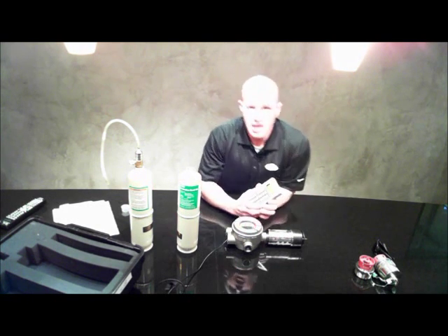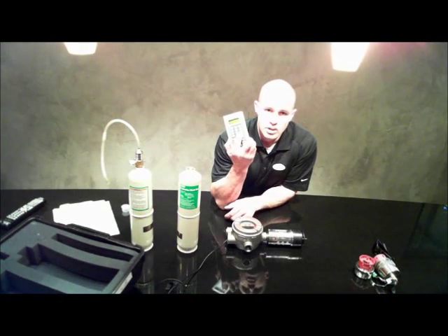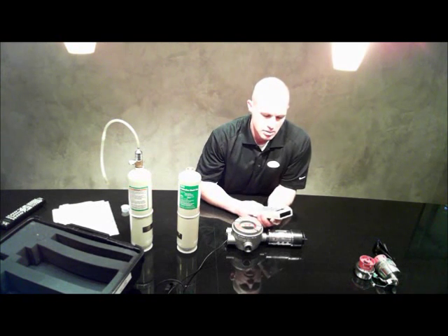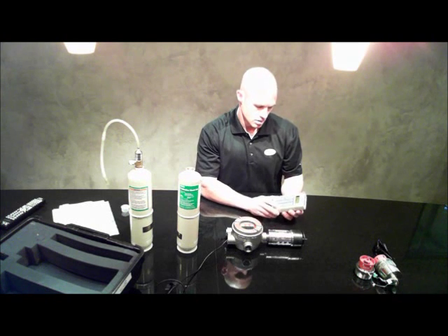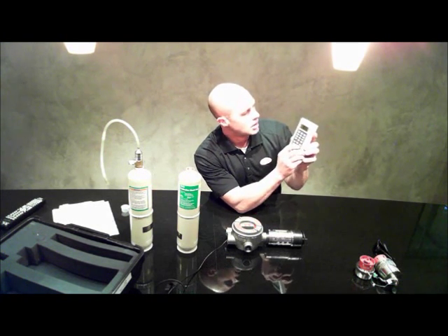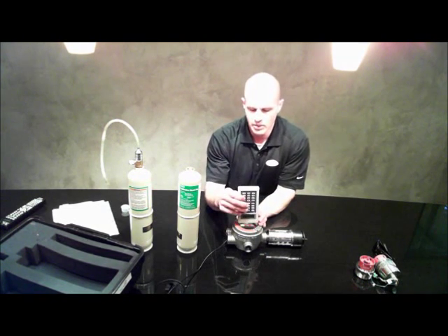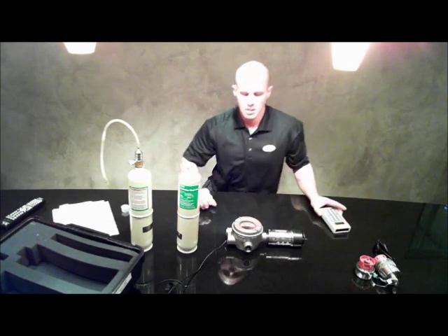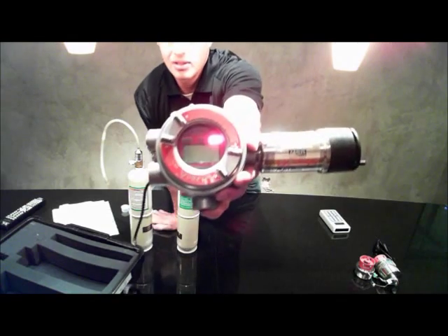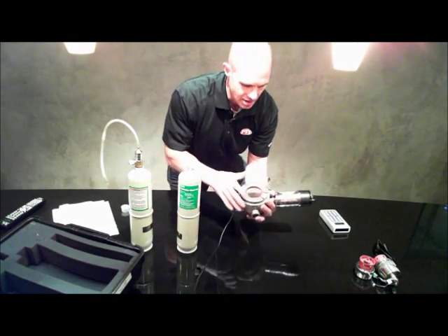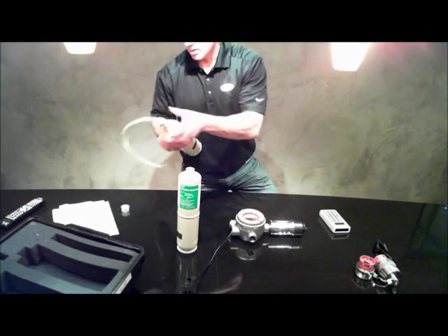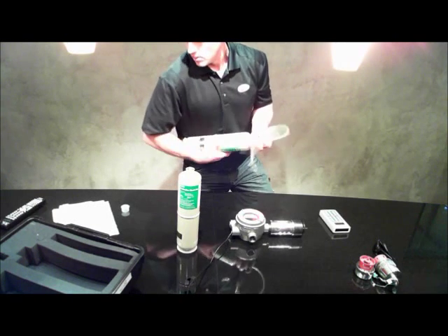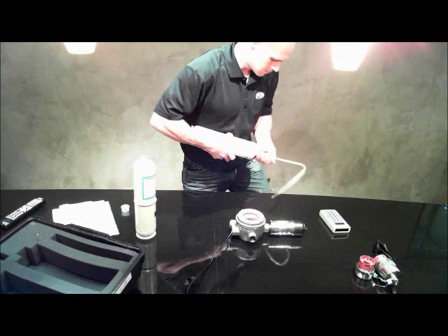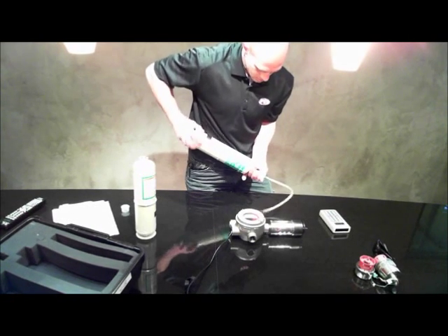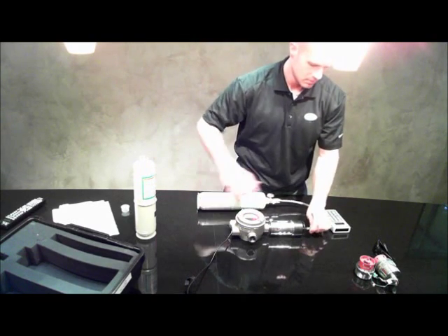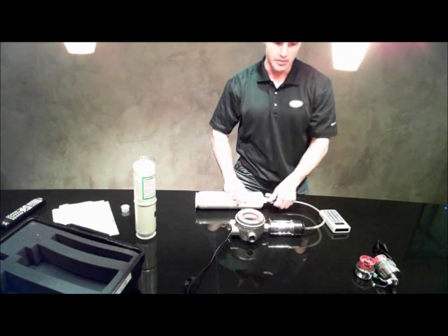Standard calibration. So for standard calibration, what I'm going to do, again, on the controller, you press enter. It'll turn on. Takes a few seconds and then it's ready. So there's a button on here that says cal. And I'm going to hit cal, but I do need to be holding it over the monitor. Now it says cal, apply 0 gas, 30-second countdown again, and crack the gas and let it flow.